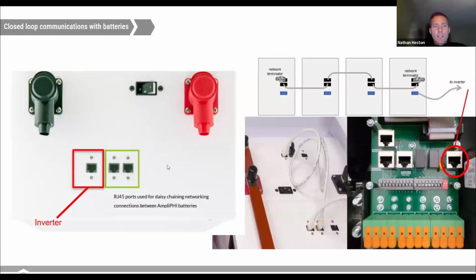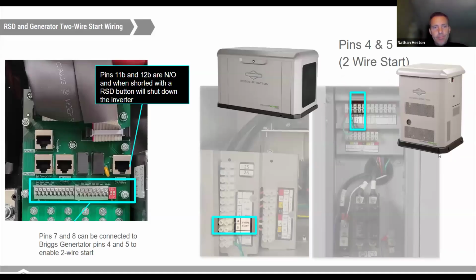Showing the use here, this is one of our SimpliPHI batteries. Closed loop comms with these batteries. Notice the use of the terminating resistor here. Those come with the batteries. You do not want to have an open port with a CAN bus communicating battery bank. So if there is any open port on the battery communications, you won't have accurate readings. And then one final home run from the battery bank device port into the inverter's battery CAN bus port. Showing that here as well.